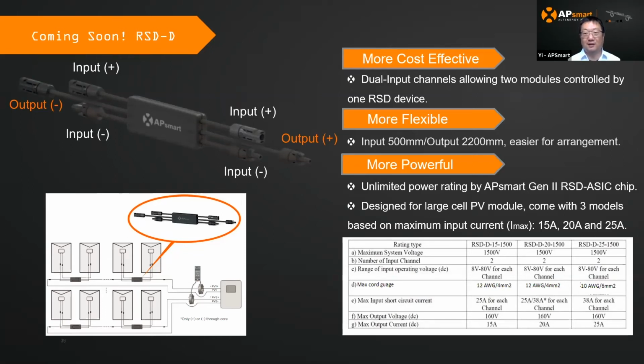And pay attention to this: the cable will be changed between the different current levels. You can see it's a 12 AWG on the first two levels, which are 15 and 20. But when it goes up to 25, it will go to a 10 AWG, which is 6 millimeter squared. So pay attention to this. The reason we can get greater input current is because we are developing the next generation of our ASIC chips to get better controllability and access to more products. Next, please.